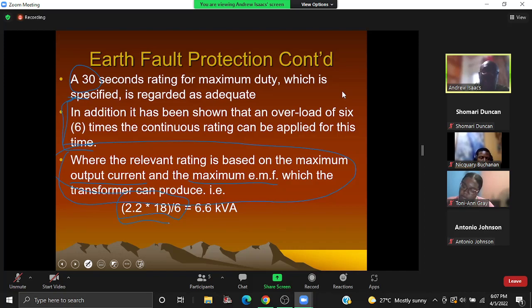So in other words, I can have a 6.6 kVA transformer as my earthing transformer because I can load it 6 times its rating for up to 30 seconds. But guess what? You can't get a 6.6 kVA transformer. So again, you're going to have to compromise. You're going to have to find something that's appropriate.